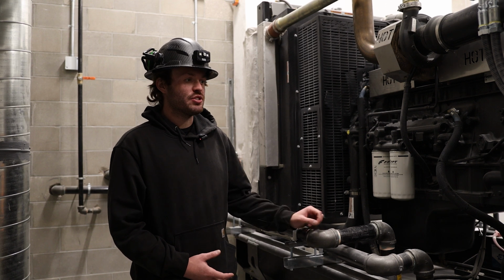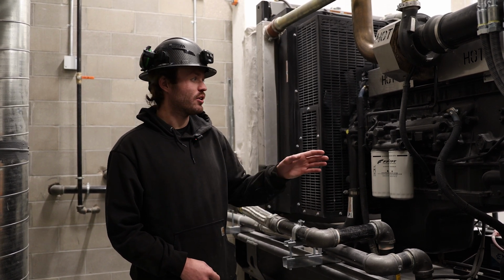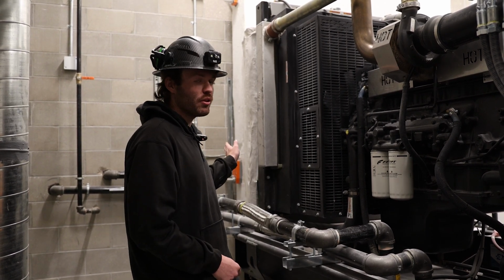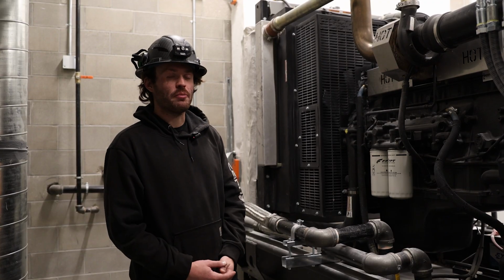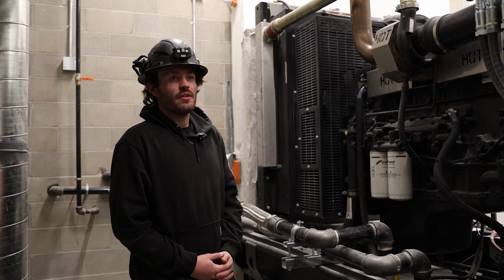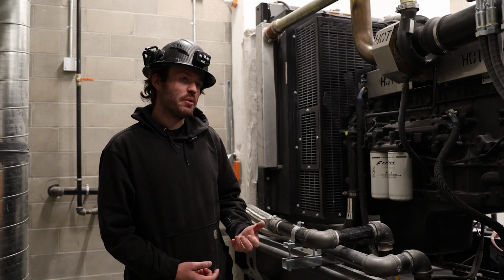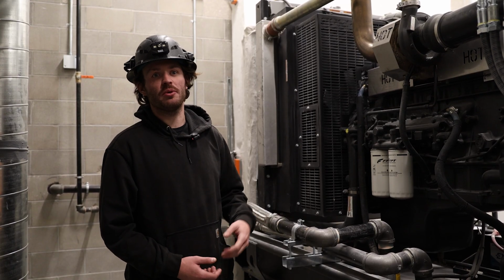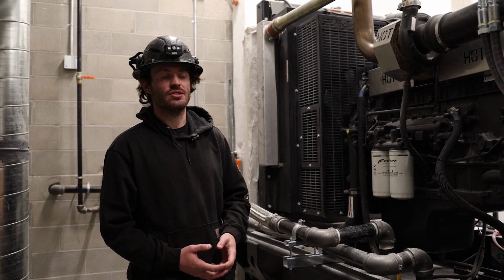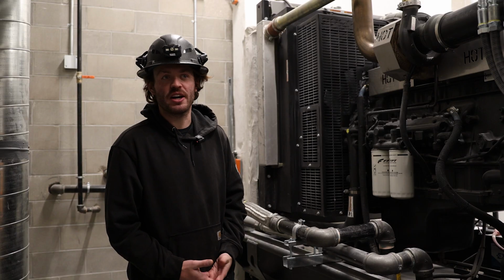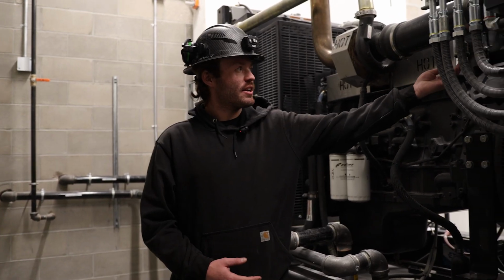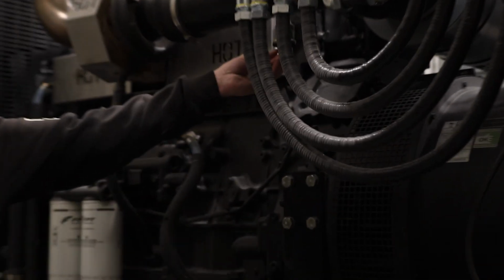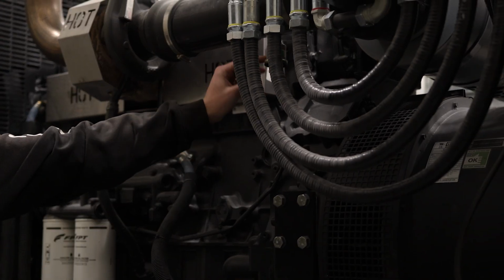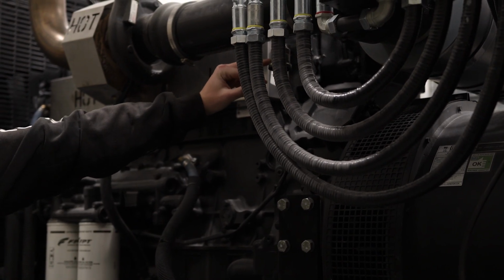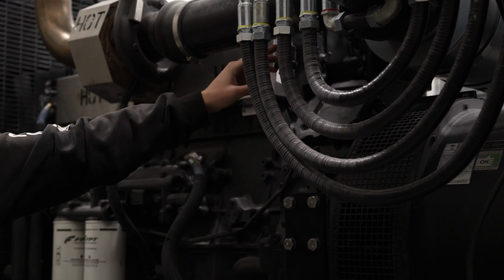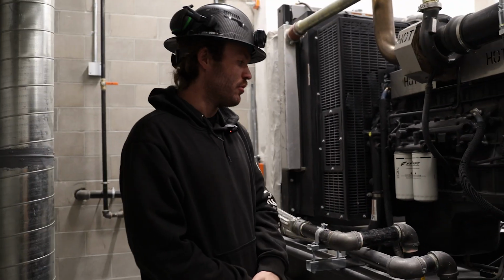So for load testing of the generator, it'll be remotely hooked up to a panel on the outside wall of the building and run at full capacity for 2 hours. This is done to eliminate a potential issue called wet stacking, as well as to guarantee the unit is fully operational to its maximum capacity. Here's the indicator for our air filter, as I mentioned on the other side. Just a little yellow line that will move up, and when it gets to the red zone, that means the air filter has become obstructed and is due for replacement.